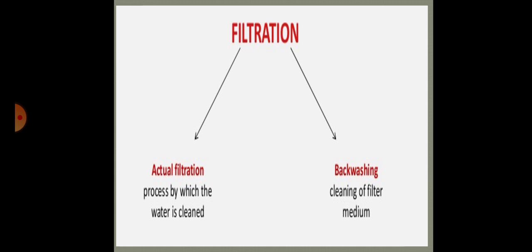Then there is the term backwashing. Backwashing is a simple process wherein the filter medium is cleaned. Like I told you, we pass water through the sand. As the water passes, the fine particles, the floc and other minerals will get entrapped between the sand particles or will fill the pores. When we treat a sufficient quantity of water, finally the pores in the sand will get completely clogged with these particles.